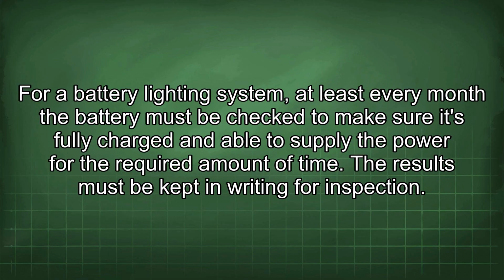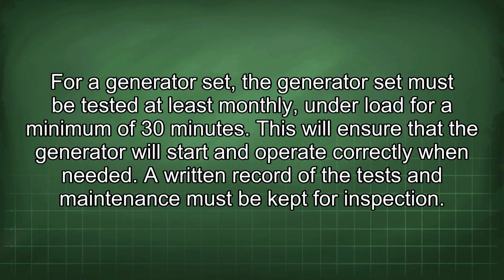For a battery lighting system, at least every month the battery must be checked to make sure it's fully charged and able to supply the power for the required amount of time. The results must be kept in writing for inspection. For a generator set, the generator set must be tested at least monthly under load for a minimum of 30 minutes. This will ensure that the generator will start and operate correctly when needed. A written record of the tests and maintenance must be kept for inspection.